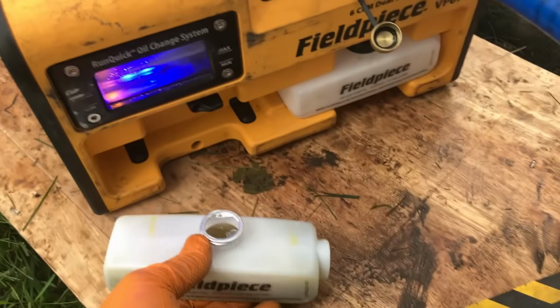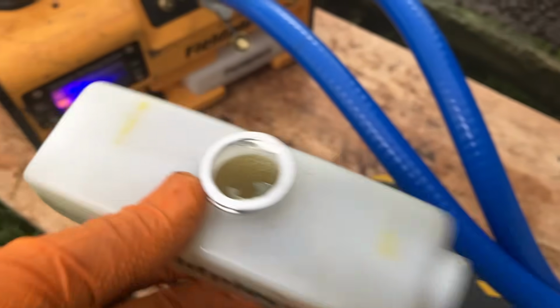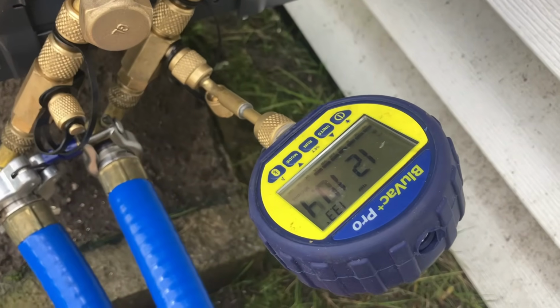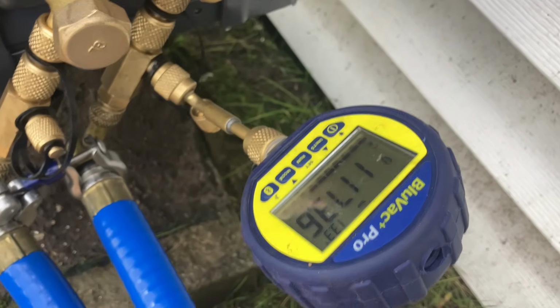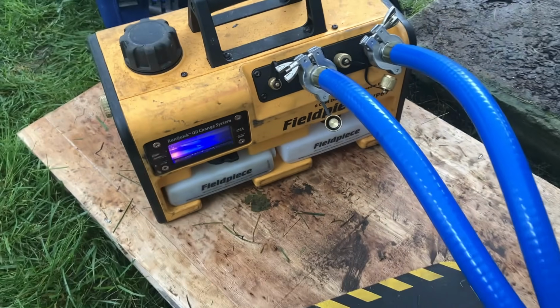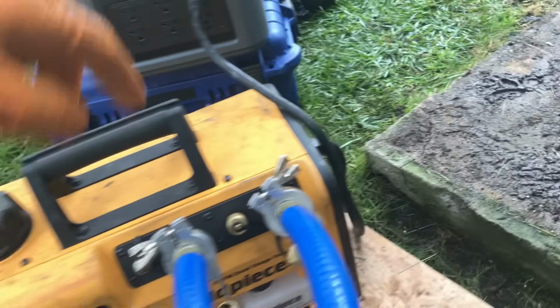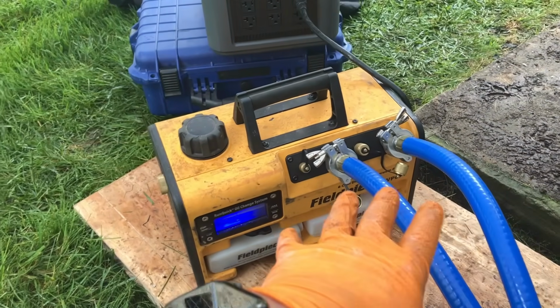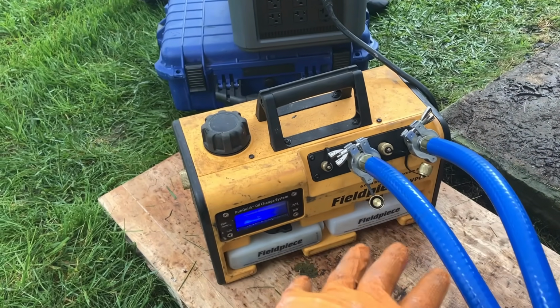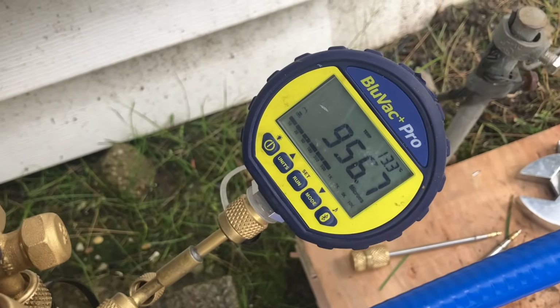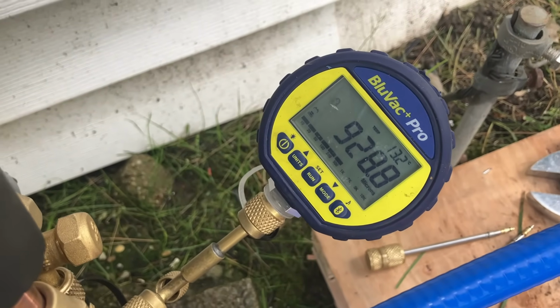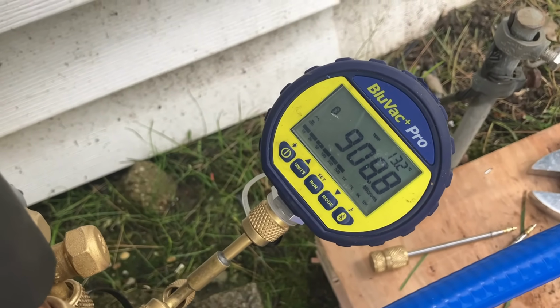Yeah, she's a little dirty. Oh yeah, she's a lot dirty actually. Woo, that's dirty. So we are at 1200 and dropping microns, we're at 1160, 50, 40. We'll dispose of the oil according to EPA and local ordinance. Let's close our ballast, and now the vacuum pump is going into a deep vacuum through that oil. Take a look at what we're working with: 956, 930, 20, 10.